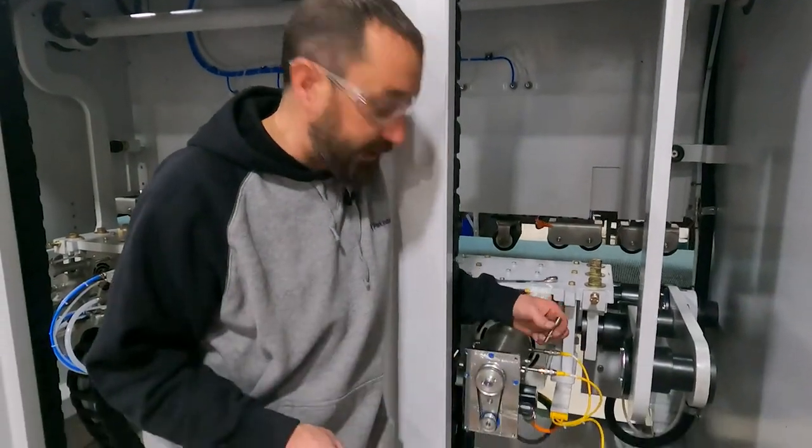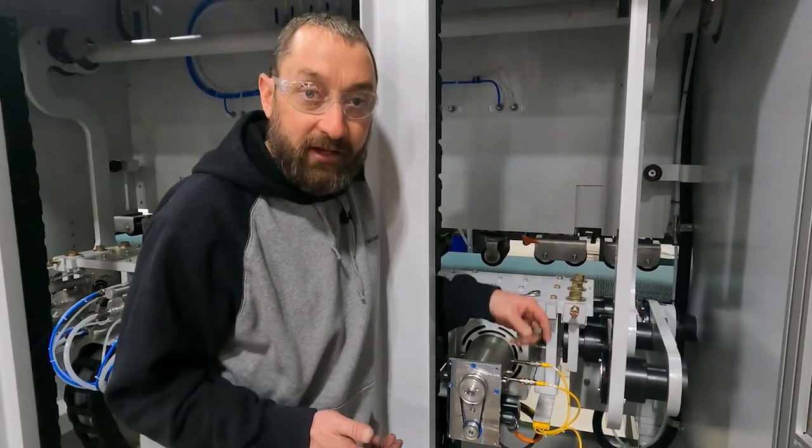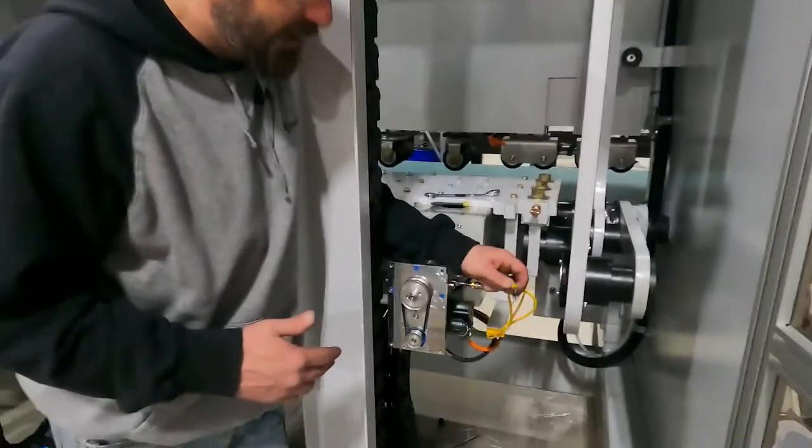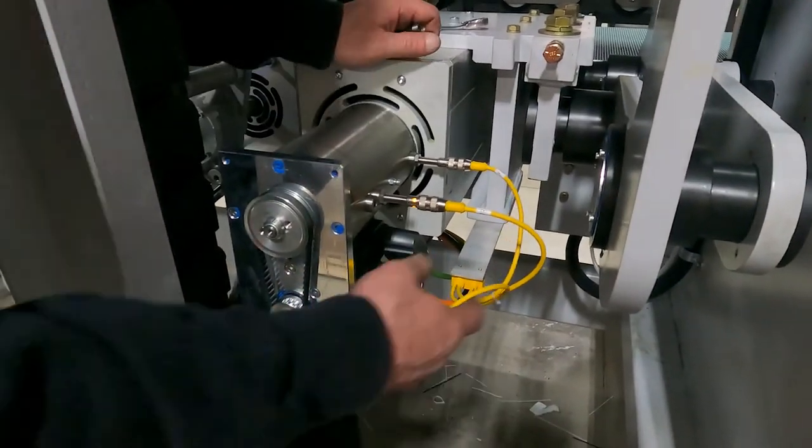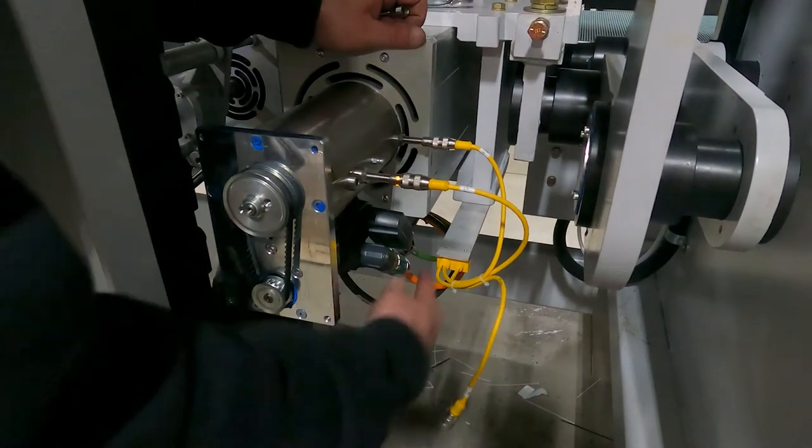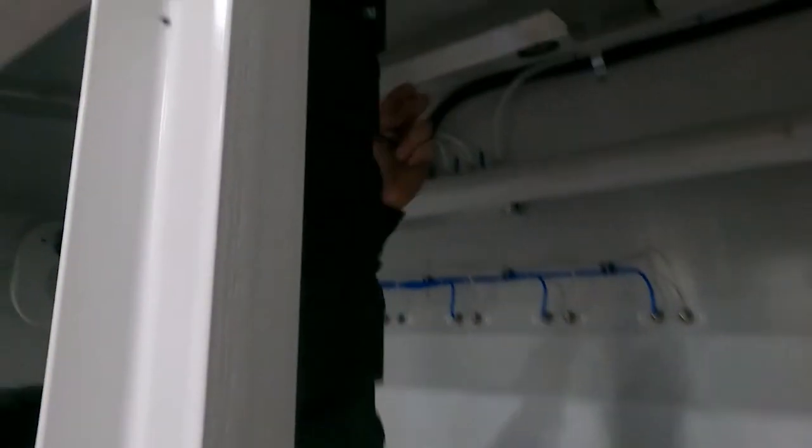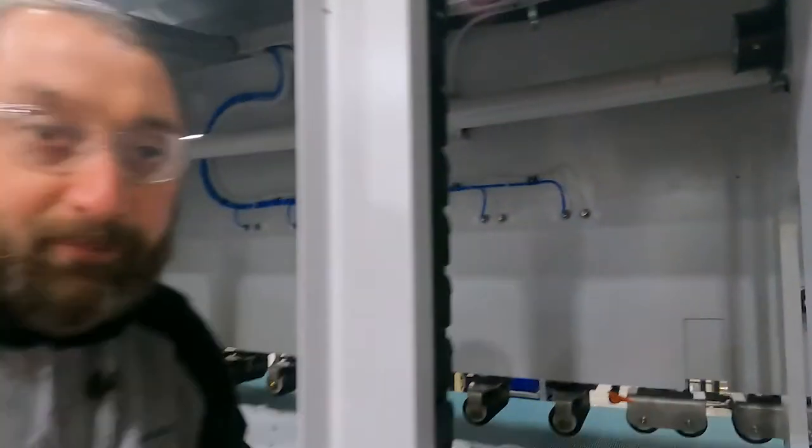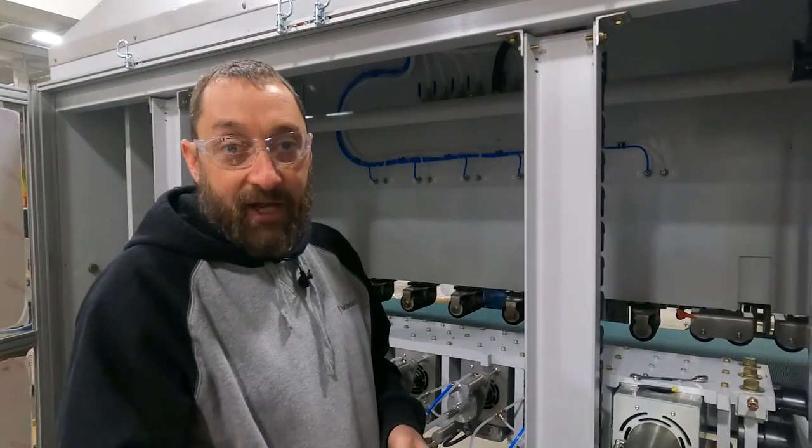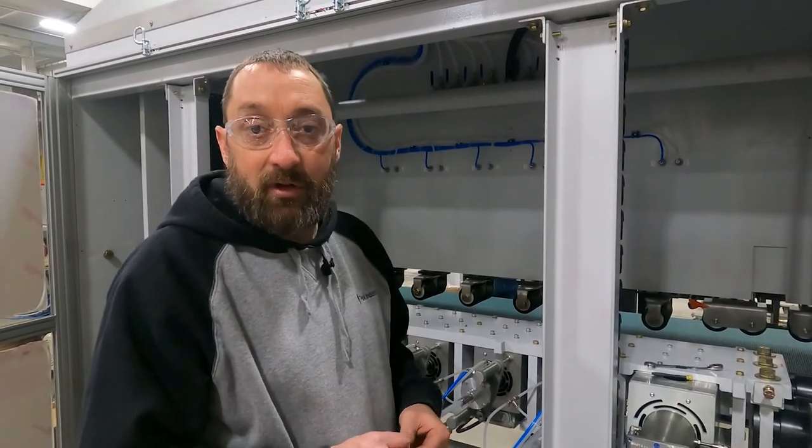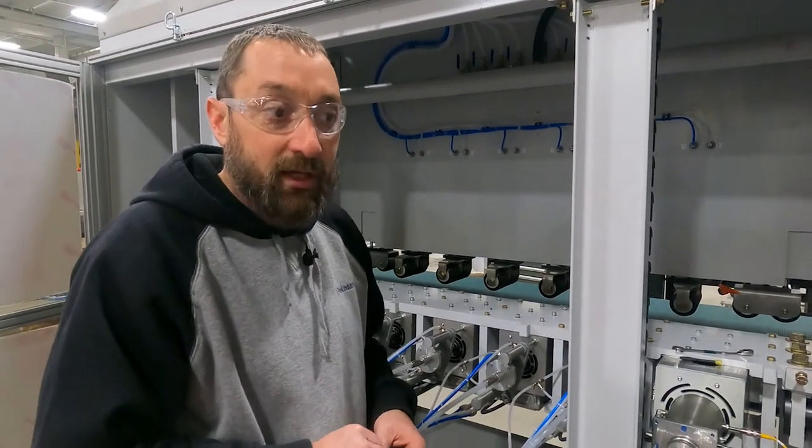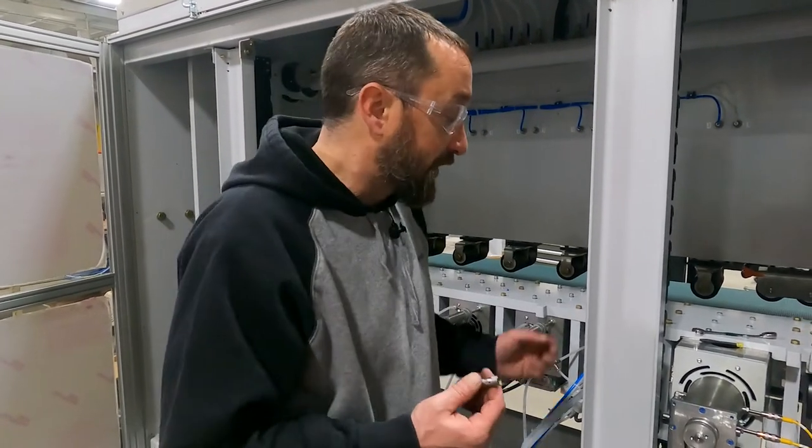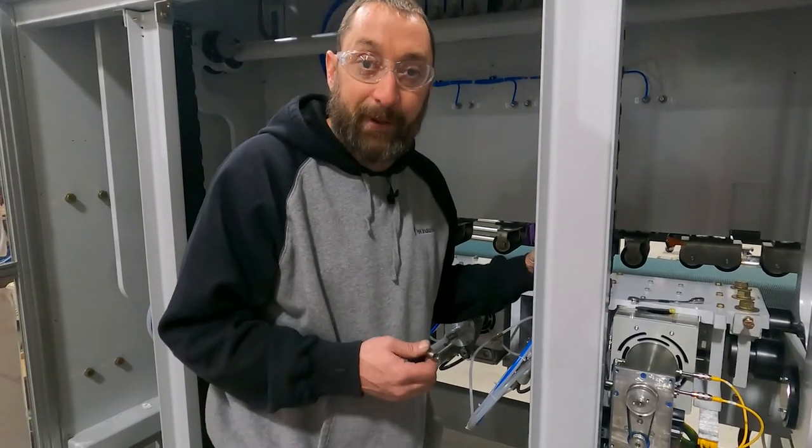Now that we're back to the backside of the machine and we know our prox and our cable are good, we're going to show how to set the prox. But first, if your cable was the bad one, you have your three that connects here, it runs underneath, goes through this track, and then about halfway up this crossmember here is where you'll have a connection point for that splitter cable. From there, you have a flying leads cable that runs back to the electrical cabinet where that terminates. Usually the flying leads cable is not the issue. Usually it will be either the prox or the splitter cable itself in the track where it's been flexing.